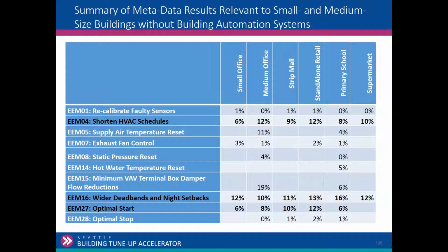if you have those kinds of systems. What's the appropriate setback? Are they using that appropriate setback? Are they employing optimum start? And you don't need a BAS system to employ optimum start. Most programmable thermostats now have intelligent recovery, so they have microprocessors. So are they programming the thermostat based on occupancy or when they want the HVAC to start? I still find a lot of confusion out there among operators as to what to set their thermostat at. Let the microprocessor decide when to start the system. And there's good savings with that.